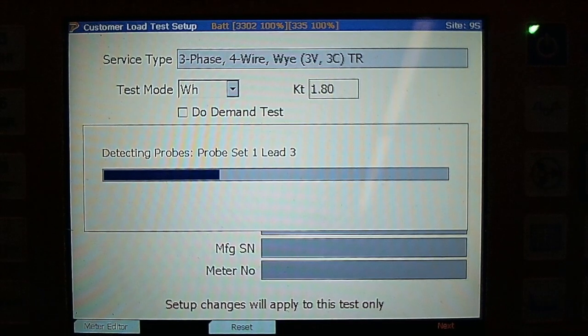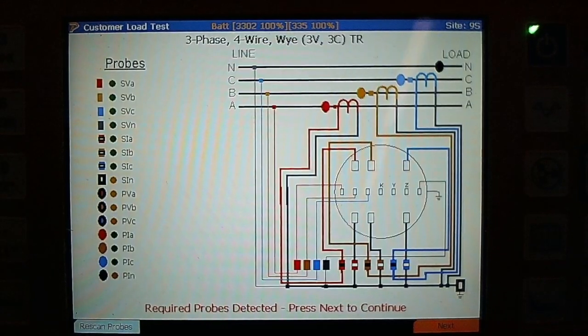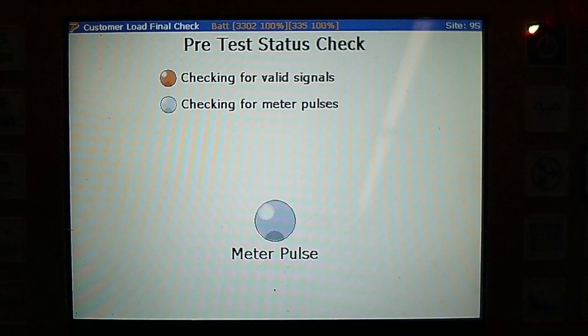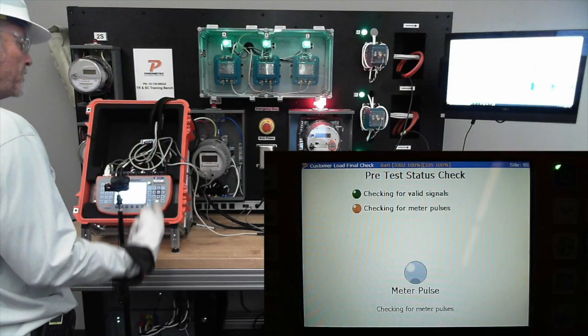And remember, the customer load test is going to multiply the voltage times the current times the power factor. It's going to come up with a number of watts, and it's going to say, okay, you told me it should be 1.8 watts every time it pulses. Let me measure the watts and see if I concur with that.